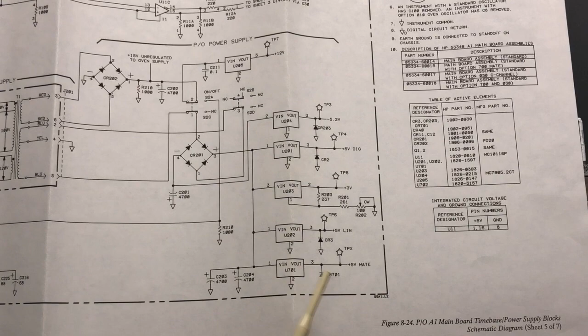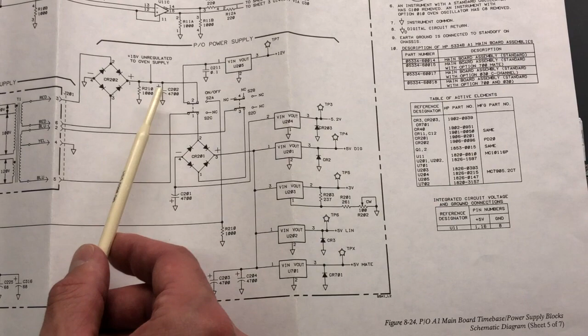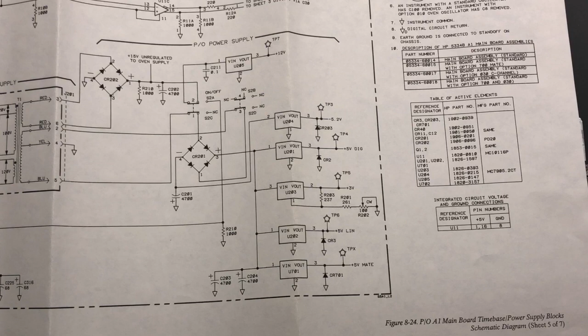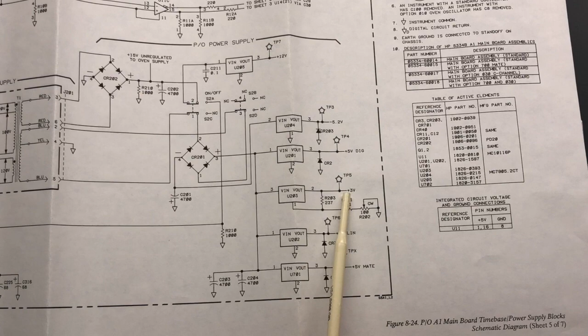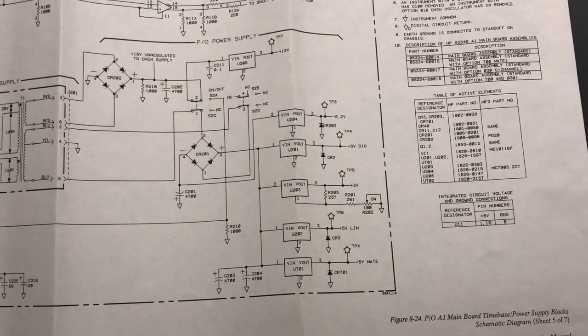These are fixed voltage regulators and there is no adjustment, but there are test points. Because we've changed these filter capacitors in here, we want to make sure that all of these voltages are looking okay, that there's no issues going on, so we'll take that measurement once we power up the instrument. But this adjustment right here is the only adjustment for a voltage, and it affects the 3-volt supply. So we'll take a measurement on the 3-volt supply. If it needs any adjustment, it's R202 that is the adjustment for that.